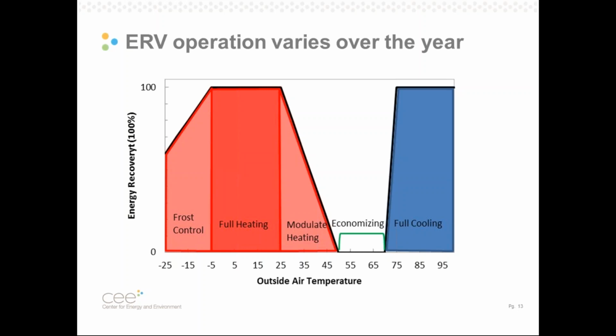At very cold outside temperatures, at iconic Minnesota temperatures, we run into another problem where energy recovery is too effective. In this case, we're not worried about overheating our supply air, but we're actually worried about overcooling our exhaust air. We're cooling down our exhaust air so much that we can put it below freezing, and we now have the opportunity to condense out moisture and freeze that moisture. And freezing moisture on ERV wheels and plates tends to block airflow, and we like to avoid it or at the very least control it.